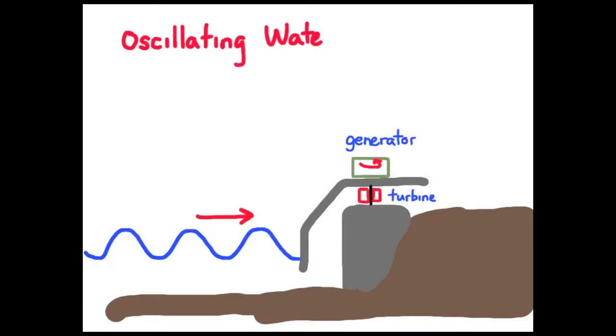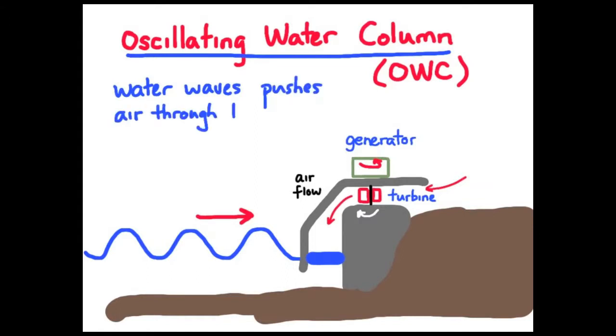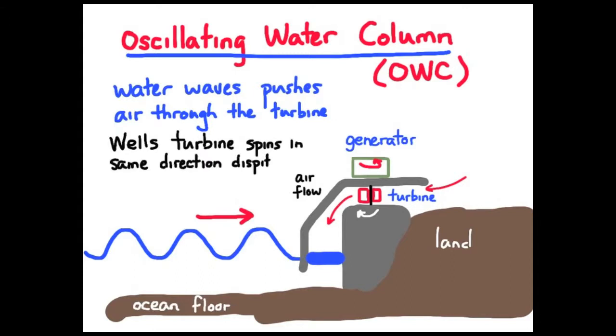So when the crest enters the ocean side of the turbine compartment, it compresses the air, forcing it through the turbine. And when a trough comes to the ocean side, it pulls air from the land side through the turbine. Wells turbine keeps it spinning in the same direction, and so you can actually generate quite a bit of electricity, even with some medium wave crests, medium amplitudes.